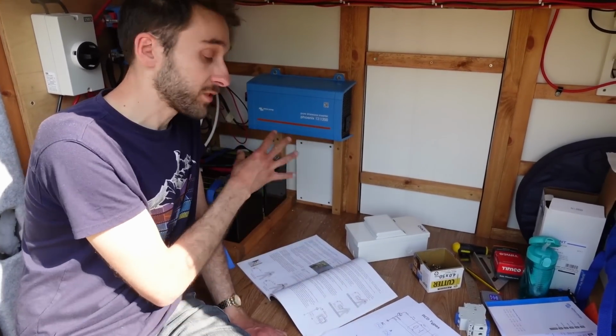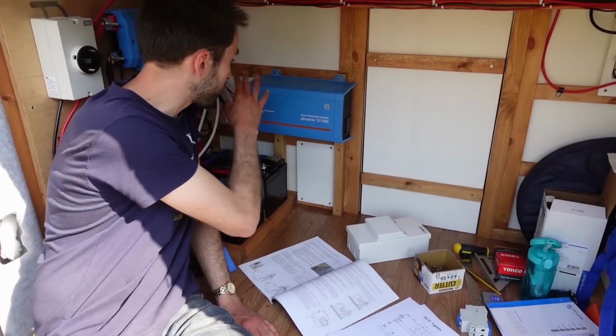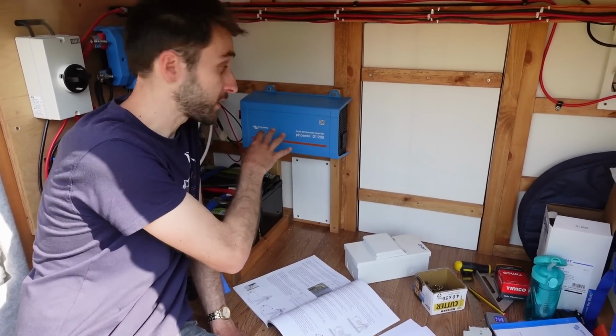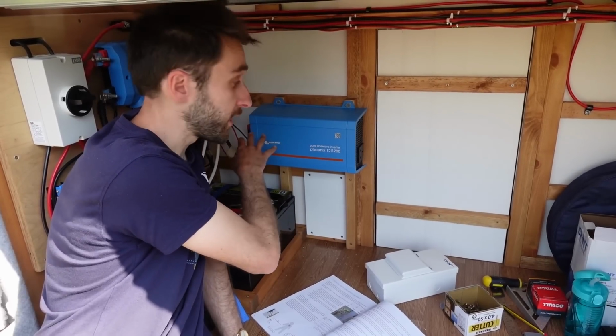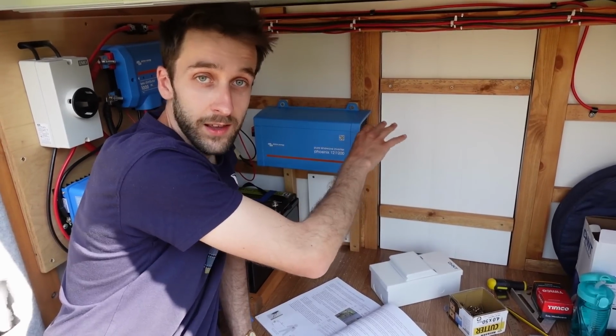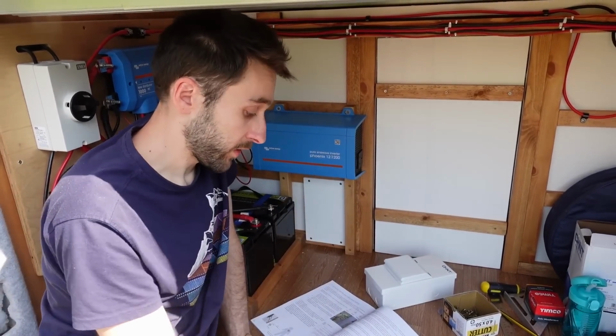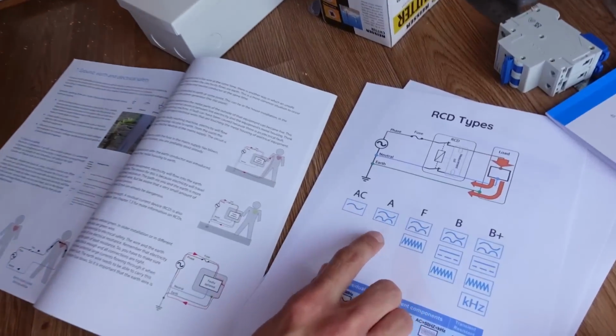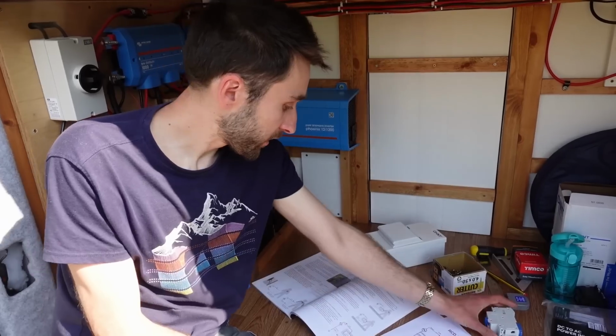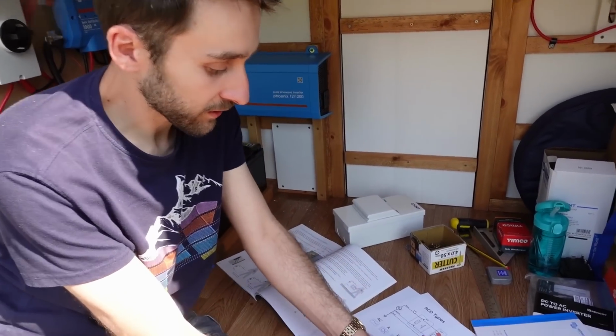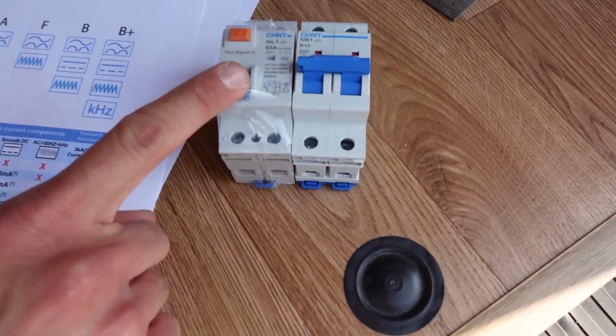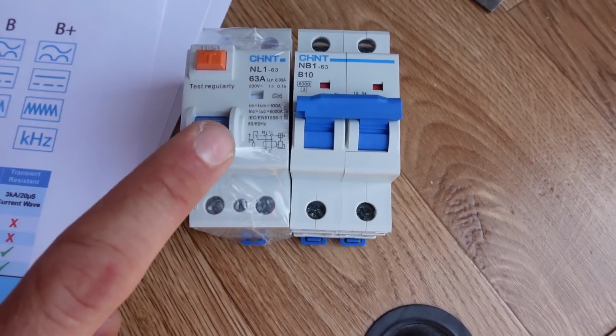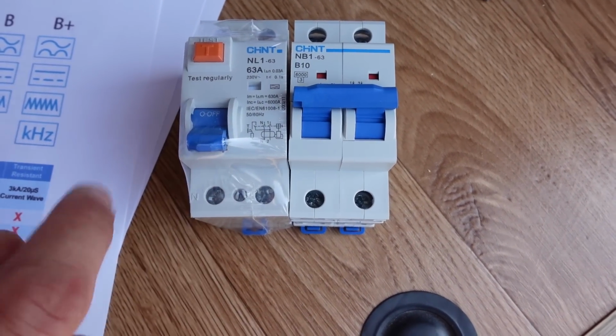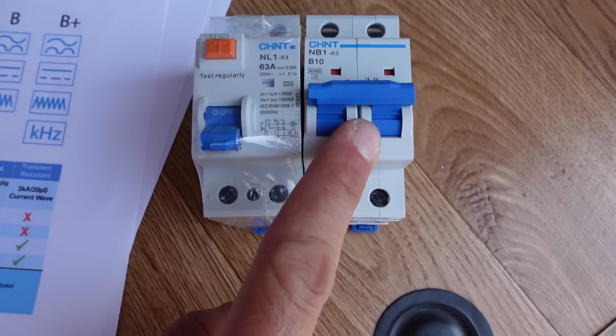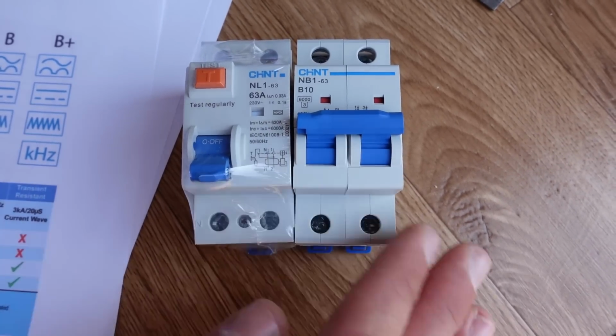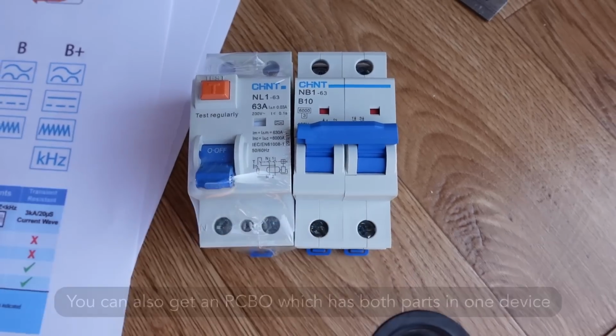And from what we've seen, actually we don't need it, because even though we've got DC and AC here, in our particular inverter there isn't a path for the DC side to actually ripple into the AC side, which means that for us we think we're okay using just the type A RCD, which is good because it's a lot cheaper. The next thing is the MCB, so that's going to go side by side like that, and this one is detecting leaking current to stop any harm to us operating it as humans, and this one is detecting overload and short circuit to actually protect the wires. So the two devices for two slightly different things.